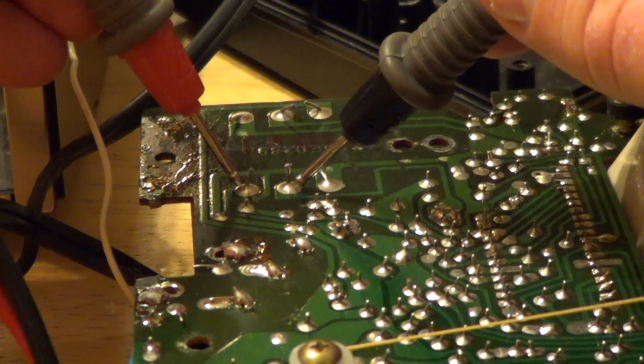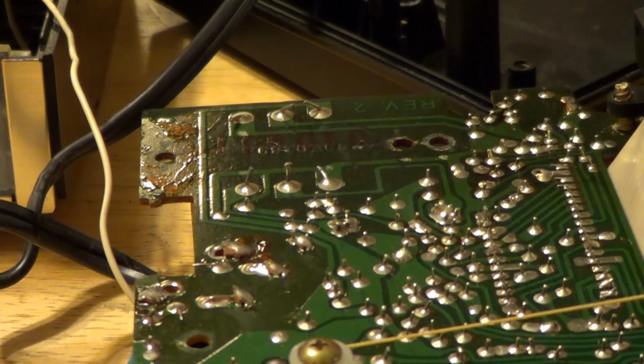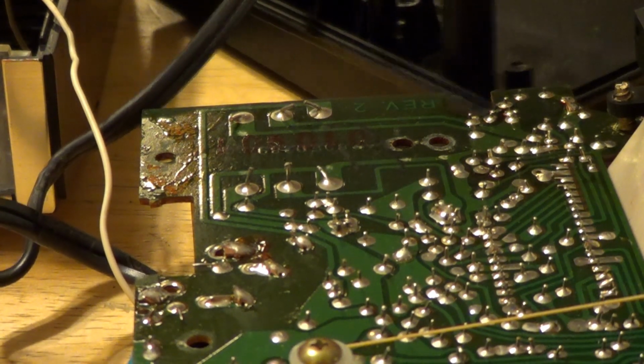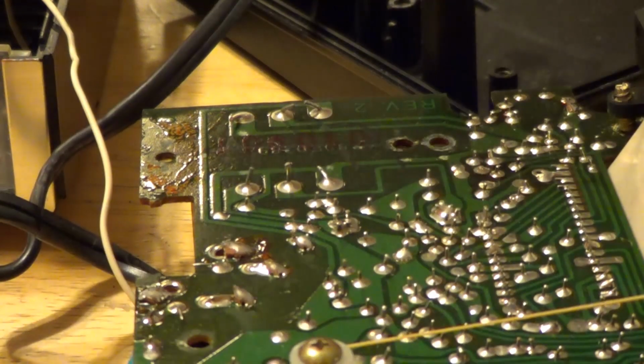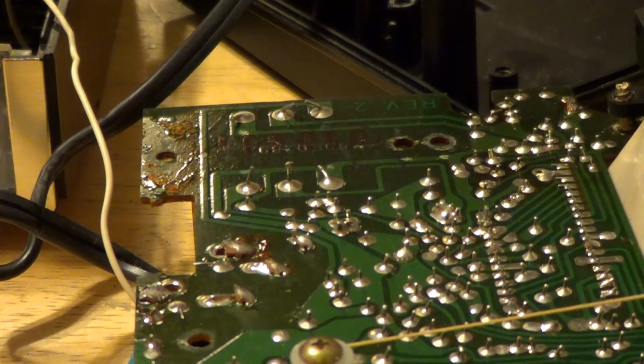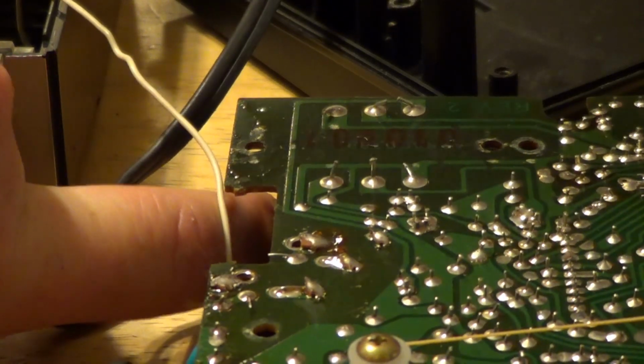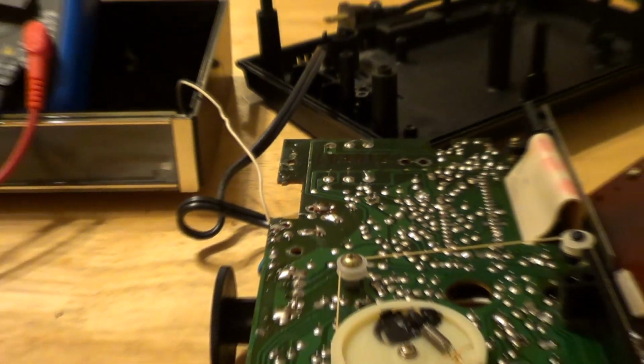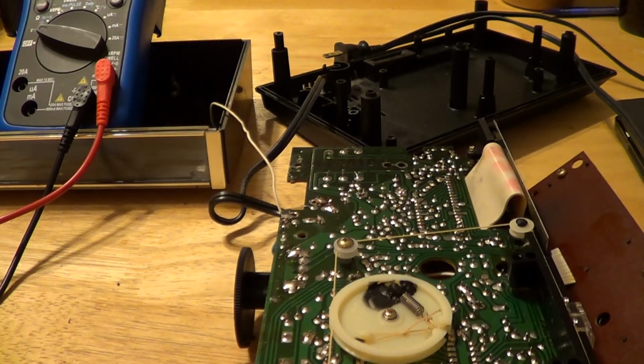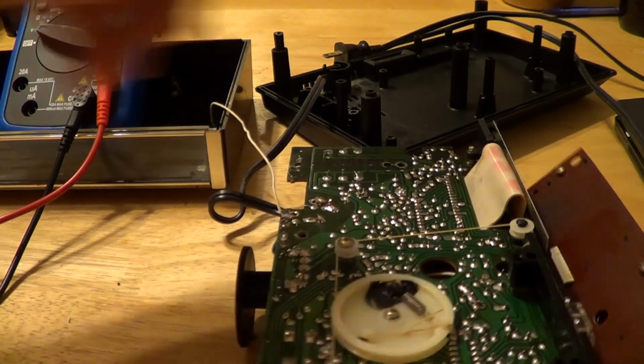So our transformer seems to be working. It could be excessively loaded in some way. There could be a fault on the secondary side. But our transformer at least does seem to be functioning, and since it's not getting very hot in operation, it's not overheating, I think we can rule out the possibility of a hard short. We're just going to have to keep looking.